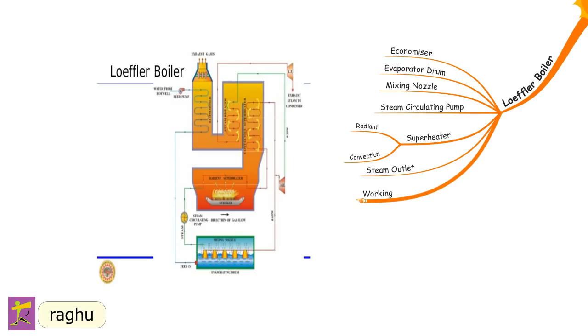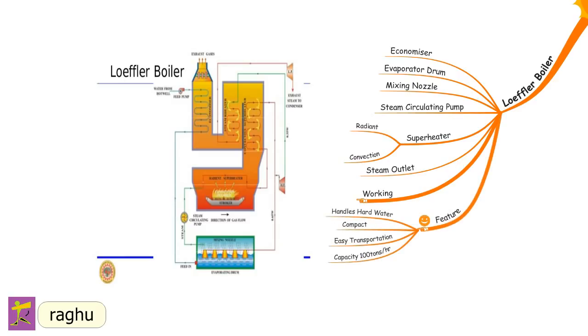In the working of the Loeffler boiler, the high-pressure feed pump draws water through the economizer and delivers it to the evaporating drum. The steam circulating pump draws saturated steam from the drum and passes it through radiant and convective superheaters. One-third of the superheated steam goes to the turbine; the remaining two-thirds passes through the water in the evaporating drum to evaporate the feed water. Features: it handles high salt concentrations, is more compact, allows easy transportation, has a capacity of 100 tons/hr, and an operating pressure of 140 bar.